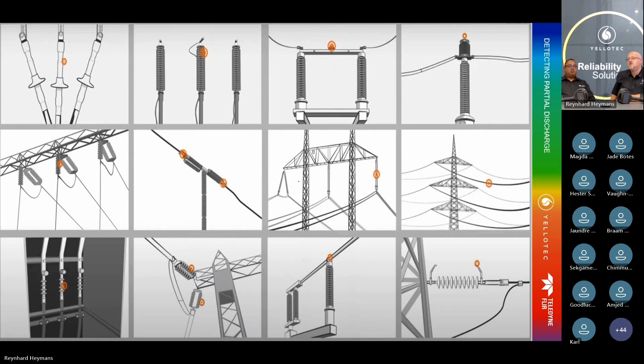Okay, so why is it bad, Ray? How often have you walked through a substation and heard the buzz? On a high voltage substation? Well, I would say most times when you walk in, you hear it. How often do you see it? No, not that often. Okay. So why is it bad? I think Ray's got a little bit of electrical background. He understands. But partial discharge causes, again, catastrophic failure if it goes undetected.